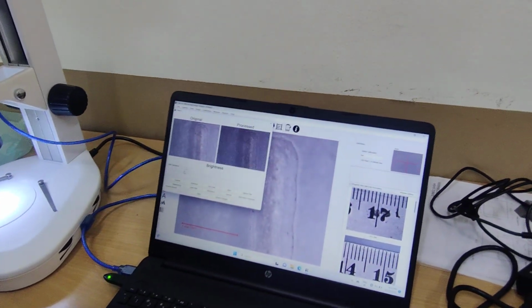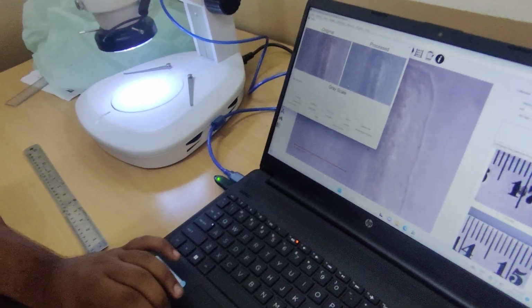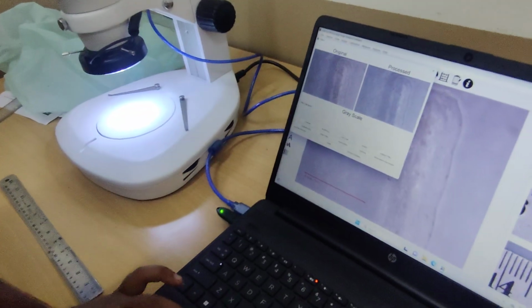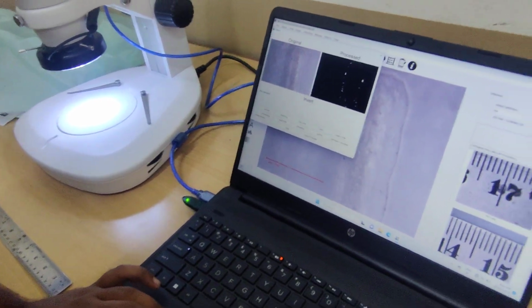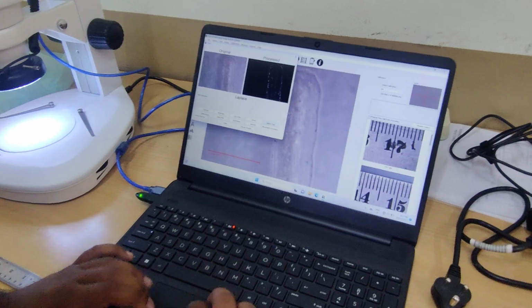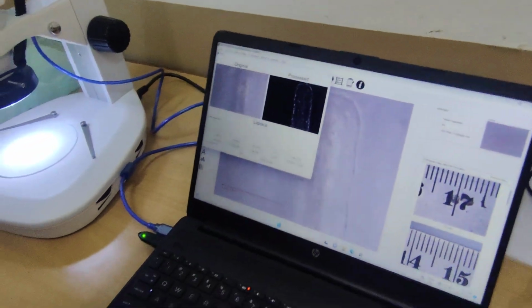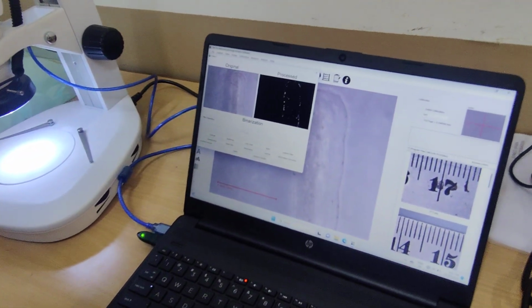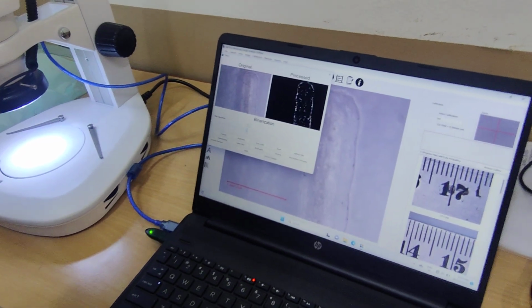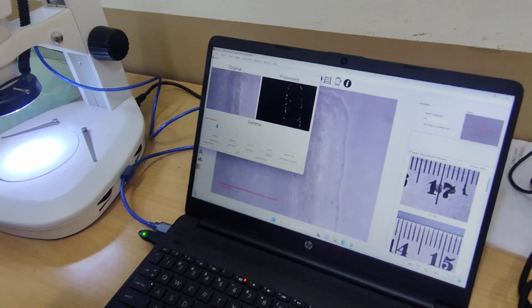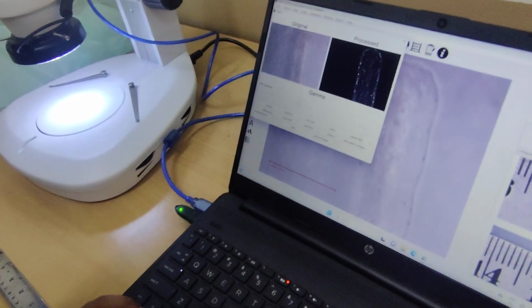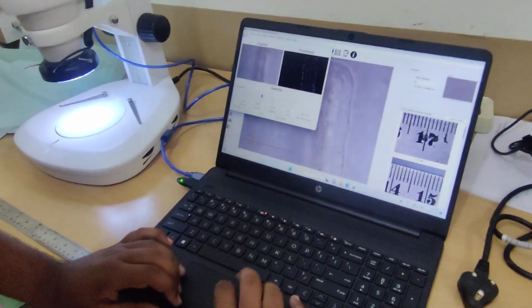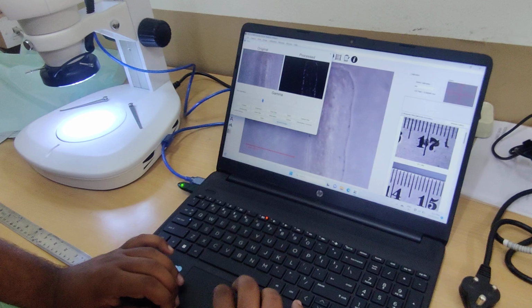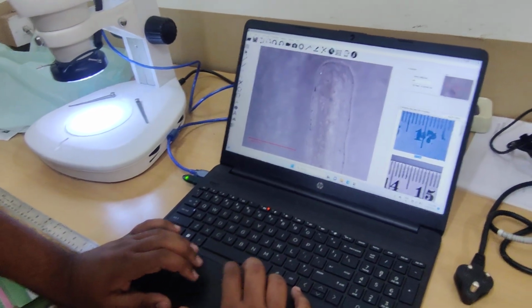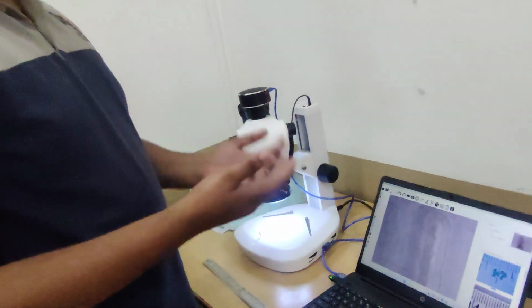You can increase or decrease the brightness, the light surrounding it, and then you can use grayscale to get a crystal clear image by removing all the noise. And then you can use invert, say, to just get the machining parts. Or you can use Laplace filter, which would just highlight where the machining is done or where the part is. And then you can click on binarization. It will just add in particles where it has happened. So the lesser the value, the more the particles, the more the value, the lesser the particles. And then you can use gamma. Gamma just filters the image, nothing more than that, but it gives you a crystal clear image of the shape. And then you can just take a screenshot of this. So this is how you can use the LifePro software to measure and analyze the machined part.